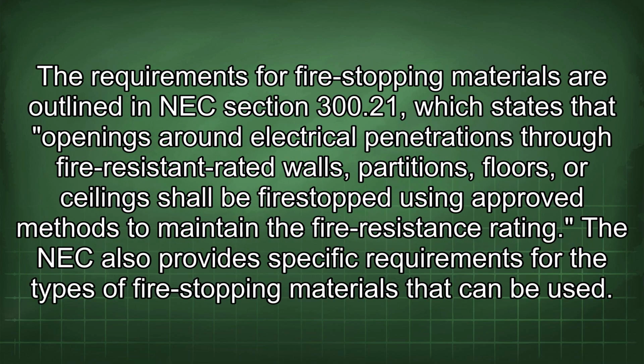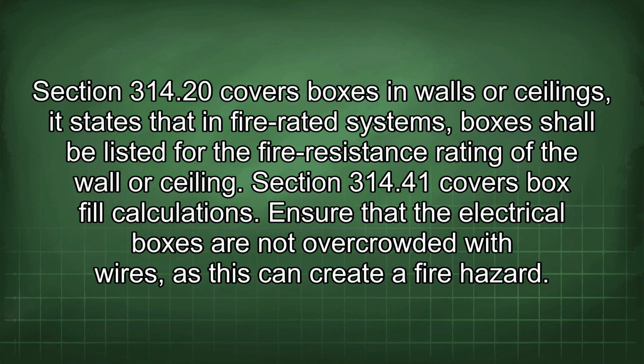The requirements for fire-stopping materials are outlined in NEC section 300.21, which states that openings around electrical penetrations through fire-resistant rated walls, partitions, floors, or ceilings shall be fire-stopped using approved methods to maintain the fire resistance rating. The NEC also provides specific requirements for the types of fire-stopping materials that can be used. Section 314.20 covers boxes in walls or ceilings. It states that in fire-rated systems, boxes shall be listed for the fire resistance rating of the wall or ceiling.